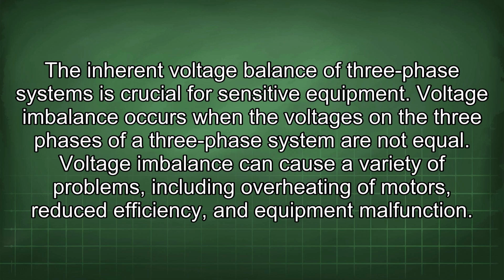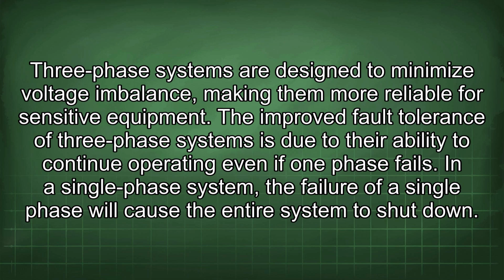The inherent voltage balance of three-phase systems is crucial for sensitive equipment. Voltage imbalance occurs when the voltages in the three phases of a three-phase system are not equal. Voltage imbalance can cause a variety of problems, including overheating of motors, reduced efficiency, and equipment malfunction. Three-phase systems are designed to minimize voltage imbalance, making them more reliable for sensitive equipment.